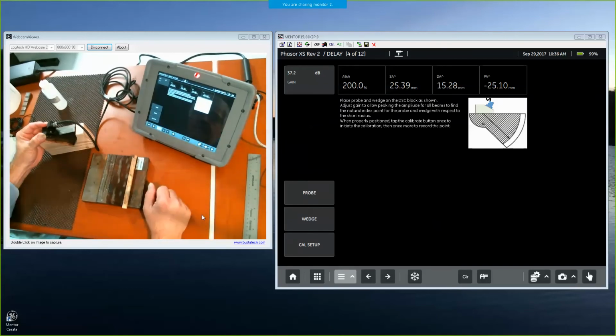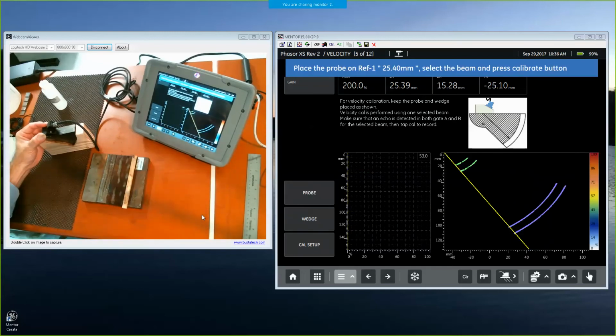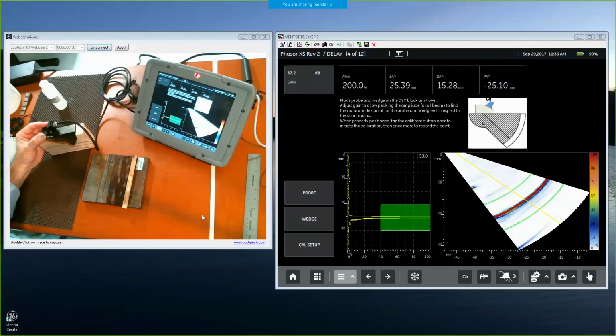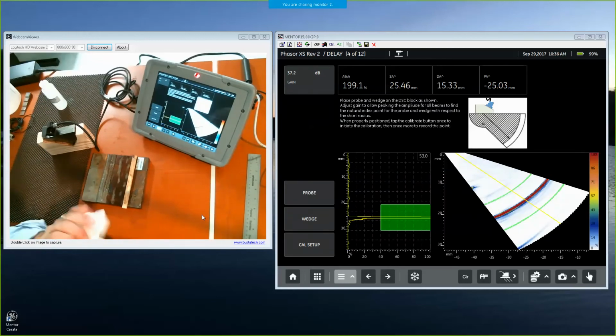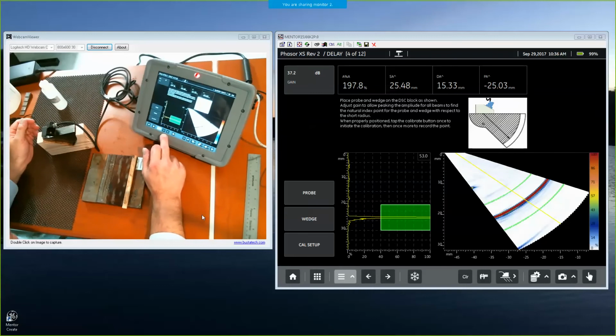Dan, this is Scott. Yeah. Can I stop you and ask you a question real quick? Sure. You said the calculation is for each beam. Is that actually done, or is that interpolated somehow? No, that's actually done. Beams individually. They're all independent zeros? Yes. Yep, the zero's done on each individual beam, and it's not interpolated. We don't, in this case, take one measurement and interpolate them. Okay. Thank you. Yep, any other questions?